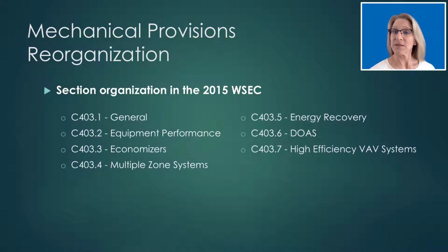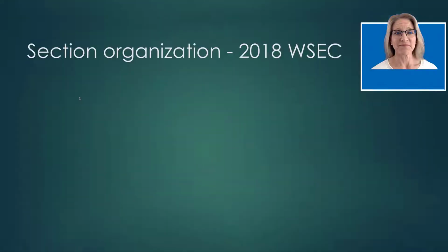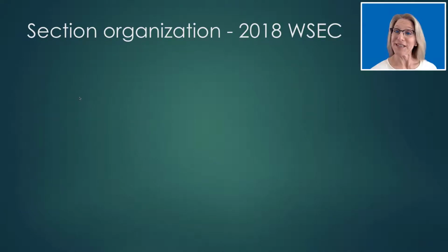the control requirements. So for the heating equipment and outdoor temperature setback requirements, they're in section C403.2. And then all the hydronic system control requirements for boilers and pumps are in multiple locations in section C403.4. So if you don't know where to look, it's easy to miss a requirement. Under the new organizational structure in the 2018 WSEC, it is now less likely that related provisions are located in multiple sections. It's not perfect, but definitely better than it was before.